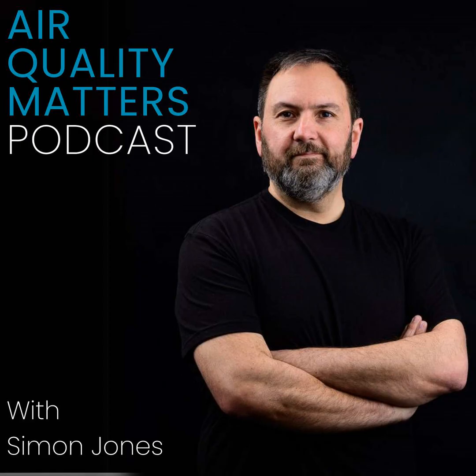But we're still seeing, as we've said a number of times in this podcast, that ventilation systems often don't deliver the airflow rates, and if they do deliver the airflow rates, they're often too noisy. And why is that? One of the main reasons in a ducted ventilation system is the ducting is inadequate. It might be undersized, might be lots of flexible ducting used, basically too high a resistance in the system.